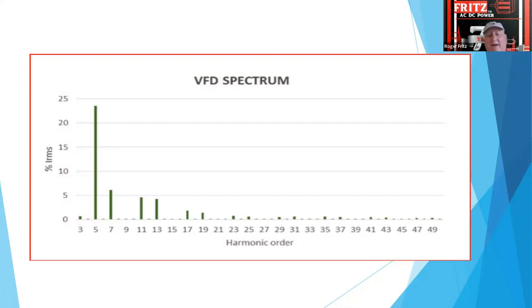which today we're actually working on a project for a company up in Ohio where they installed about 40 VFDs in a data center. They also have the data center loads in there. They have the chillers, and because the building is not loaded as heavily as it was in the past because of COVID, the chillers are not running at full load. Some of them had VFDs on, some don't. And literally it's thrown the power factor off to like 69%. And for any power factor below 70%, the power company's hitting them with a $25,000 a month penalty.